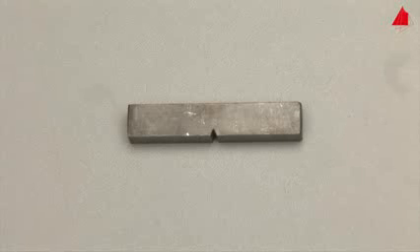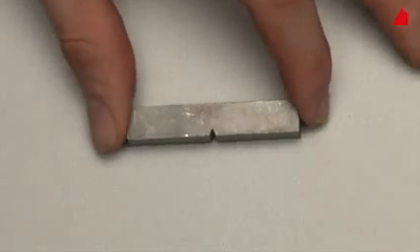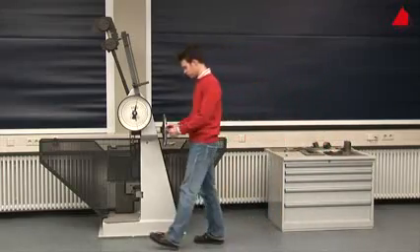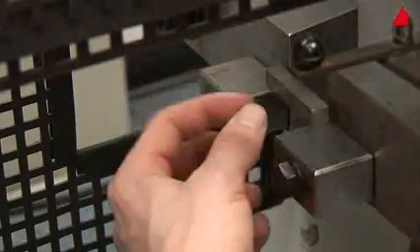This is our test specimen. It has been machined to standardized size and shape with the characteristic V-shaped notch. The tester places the specimen on a support in the lower part of the machine and adjusts its position with a centering device.